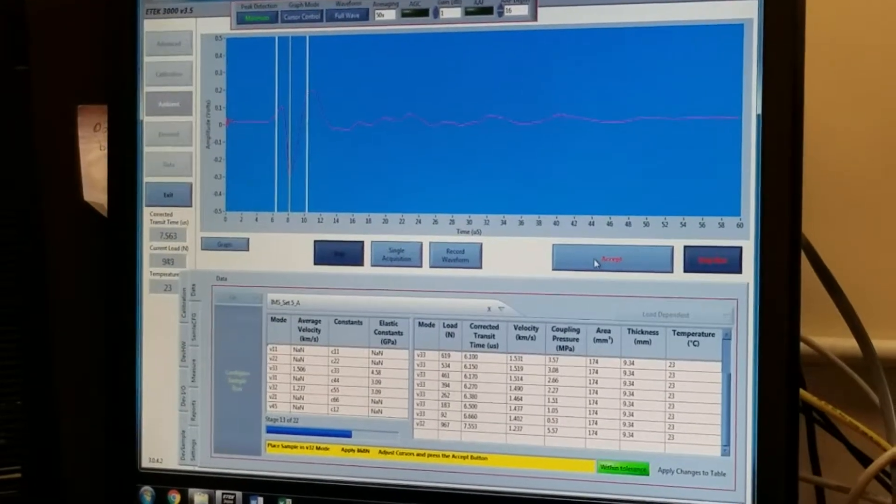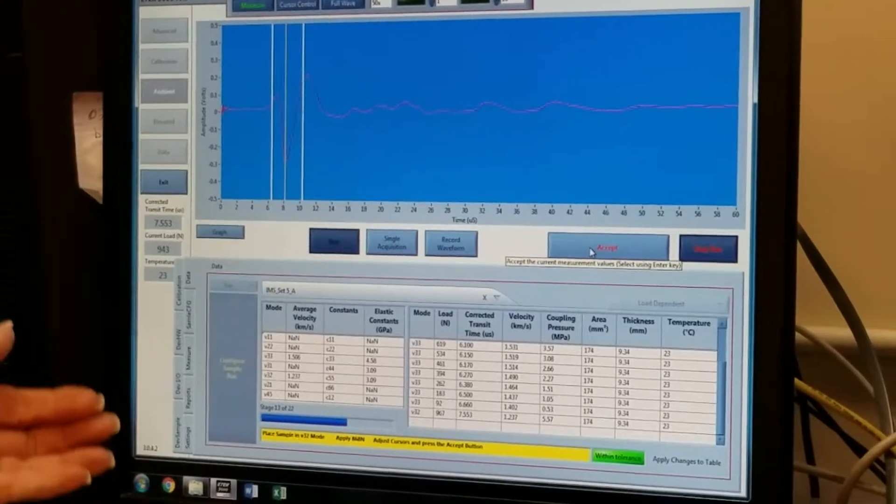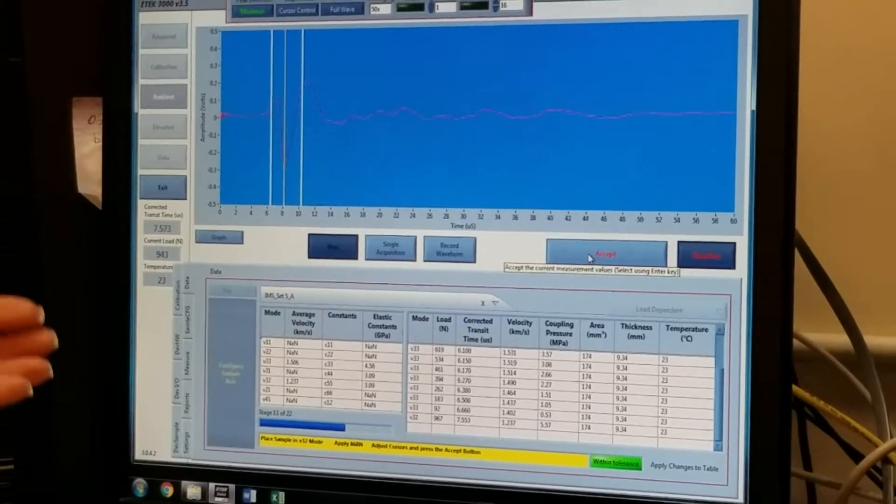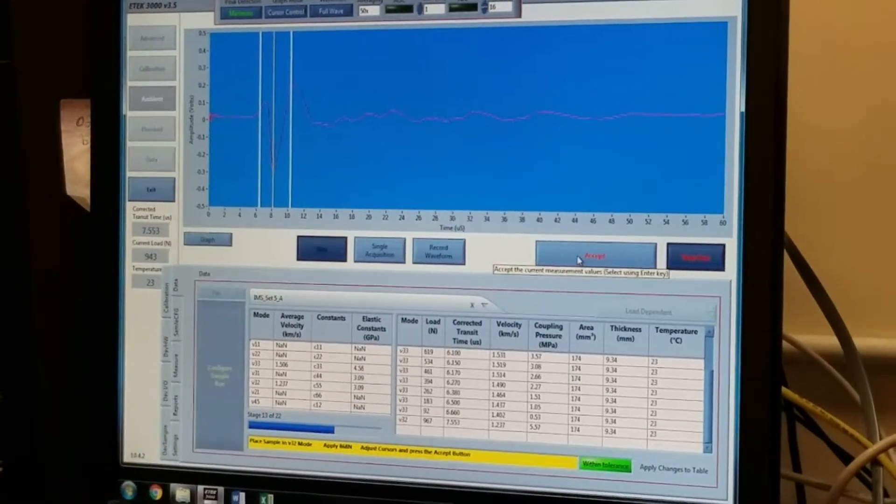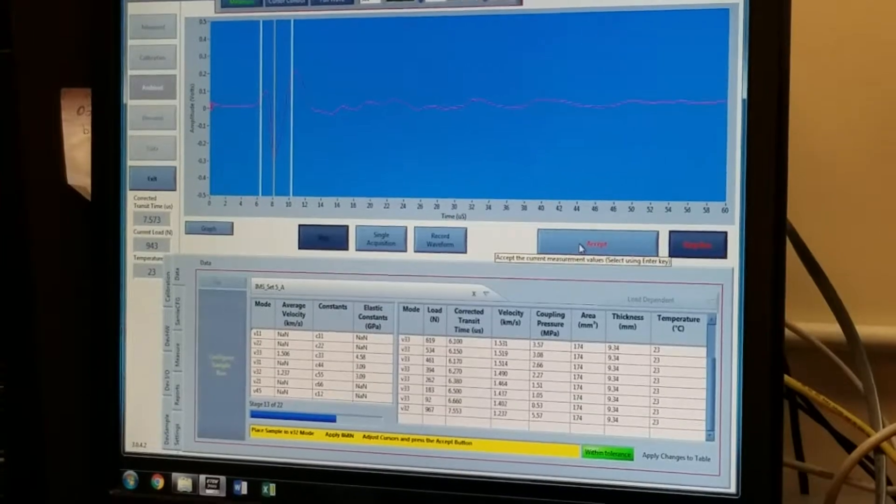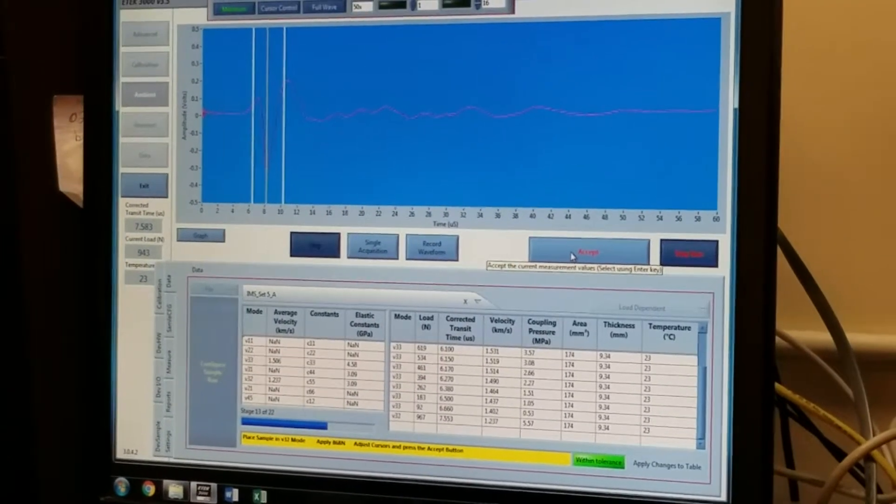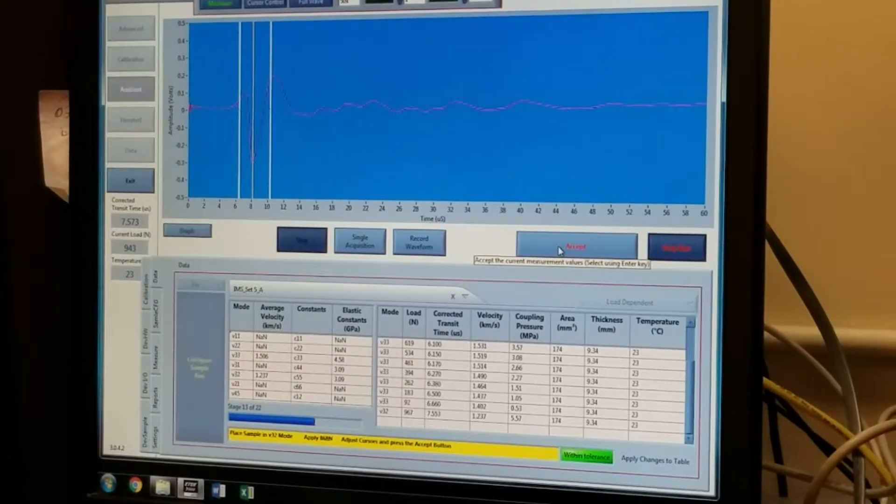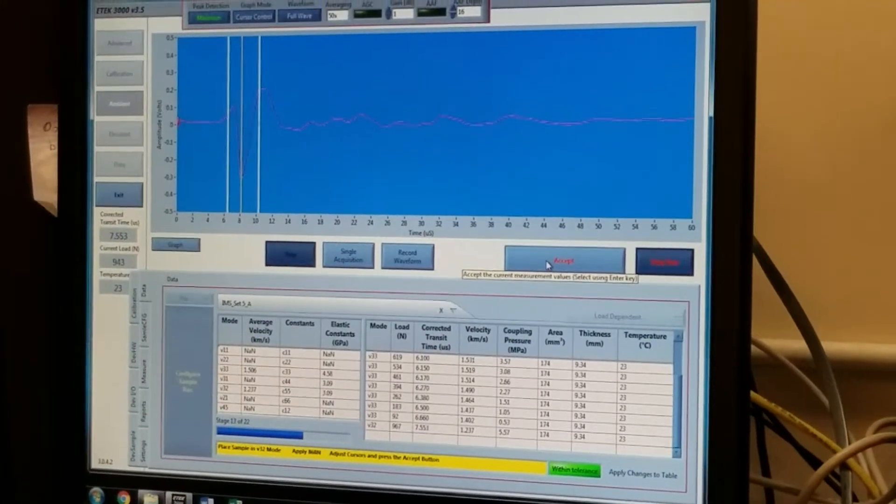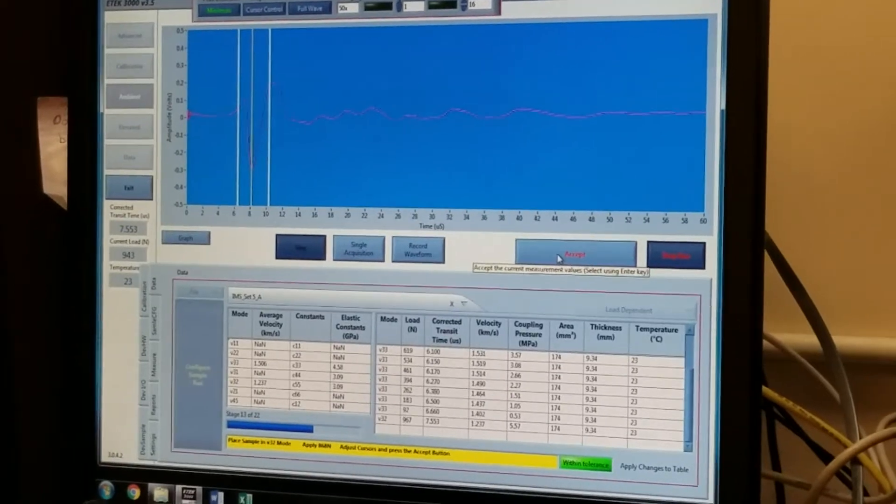And the prompt now is going to say apply 800 newtons and increment down to 89 newtons, just as we did with the compressional measurement.